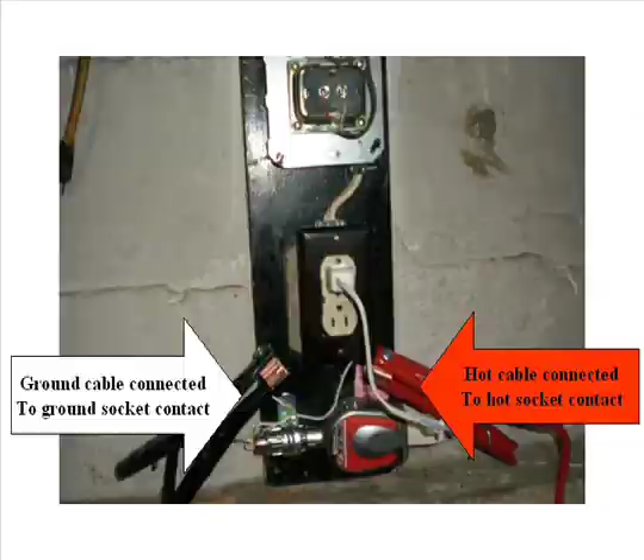When you are not using this device to fire up the burner, be sure to unplug the unit from the outlet before turning on the main power to the transformer. So when it's not in use, leave it unplugged. It might even be a good idea to put the plug away somewhere so nobody can inadvertently plug it in, because that could ruin the power inverter.